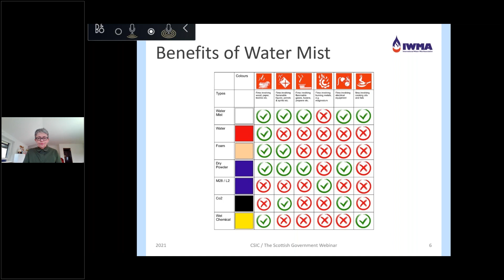In this chart, you can see that water mist ticks nearly all the boxes, more than other fire suppression systems. I'd like to explain the two columns on the right-hand side: electric and cooking oil fires. With water mist, we're not looking for the water itself to extinguish the fire, but the mist. We want the droplets to turn into mist by making sure it hovers above the flames and then sinks down. The nozzle must therefore not point into the flames.